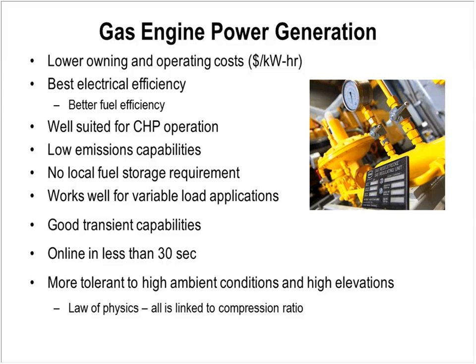Life to top end on a diesel in a prime power application could be in the 8,000 to 10,000 hour range. On a gas engine, you could easily get into the 20,000 to 30,000 hour range, and a major overhaul on a gas engine is commonly between 40,000 and 80,000 hours. So significantly longer life to overhaul, a lot of which has to do with the type of fuel.